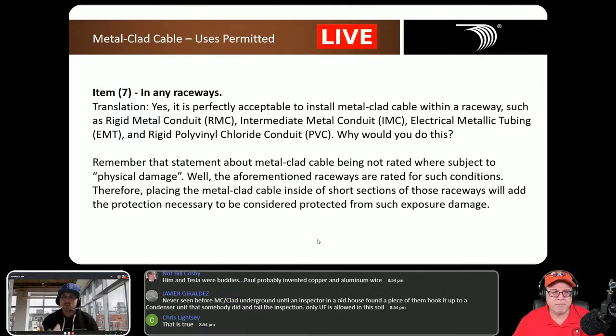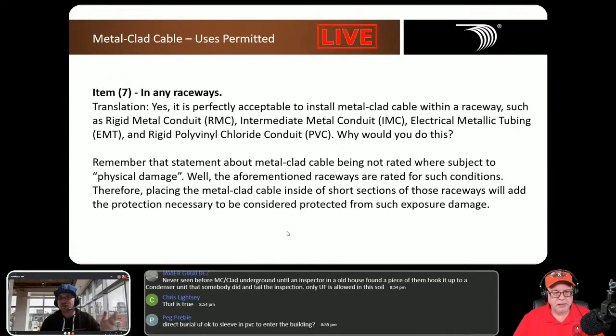Okay, not a problem. Didn't I tell you when we were talking about the MC that I installed outside? I said, well, I guess I could have just put it in a piece of liquid tight. And you said no, because that raceway outside is still considered wet location. Yeah, so if the product is rated for a dry location and you put it in a wiring method outside, it's still a wet location. And right, even though somebody wants to say liquid tight, it ain't never going to be liquid tight, Jay.